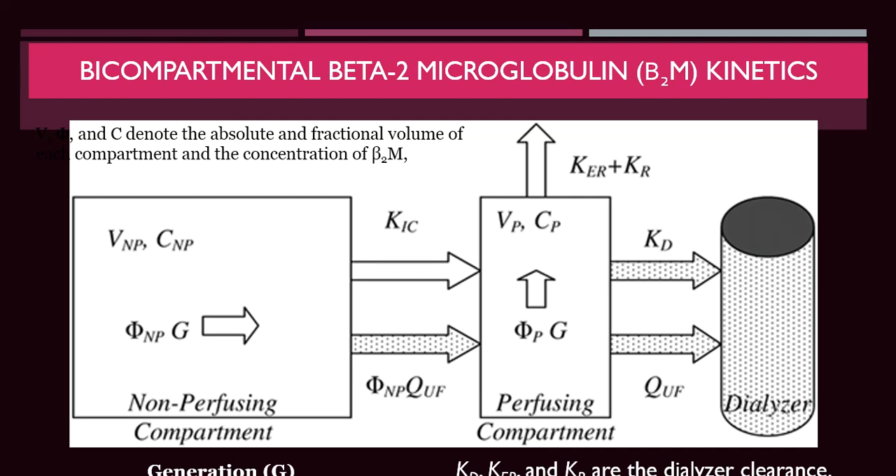In the bi-compartmental model, removal from the perfusing compartment through the dialyzer depends on two main factors: the clearance criteria of the dialysis membrane — high-flux versus super-flux — and the QUF. Increasing ultrafiltration rate, as in HDF, removes much more beta-2-microglobulin. Both dialyzer clearance and ultrafiltration rate together increase the removal of beta-2-microglobulin.